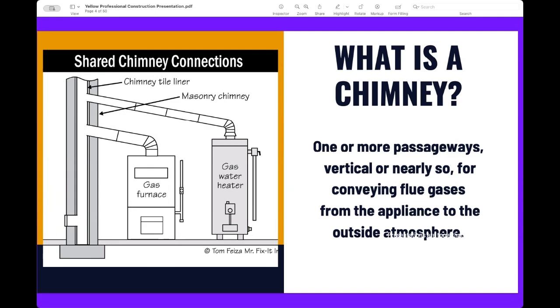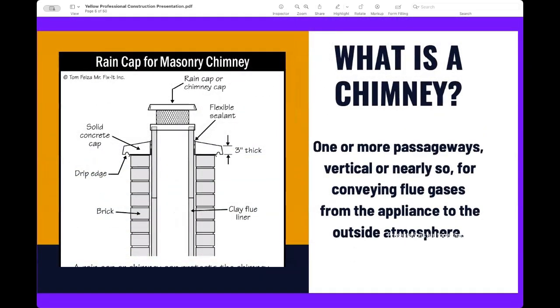Now, is that what's called an orphaned water heater or an orphaned exhaust? Yes, that's a common term for the water heater that is left over when we replace the gas furnace. And because it's just too small, when the exhaust is coming out, it's got room to just float around as opposed to just being sucked up. Correct. We can't rely on gravity to act, and the Bernoulli effect of getting the hot air all the way to the top of that chimney.